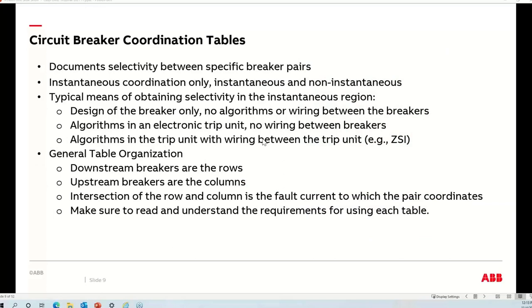How do I know if a circuit breaker is going to coordinate in that lower instantaneous region? Circuit breaker coordination tables will guide you. It is a document that each major vendor produces that allows you to identify specific breaker pairs and the level of fault current to which they coordinate. Different vendors will have different styles of tables — some cover instantaneous coordination only, while some are designed to give information on both the instantaneous and non-instantaneous parts of the breaker curves.